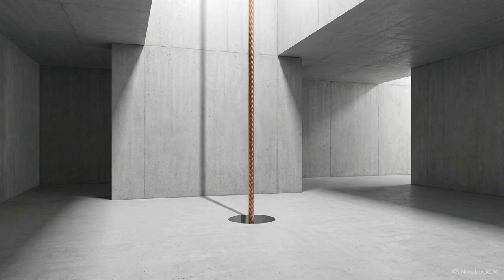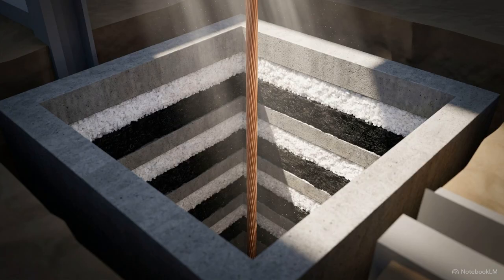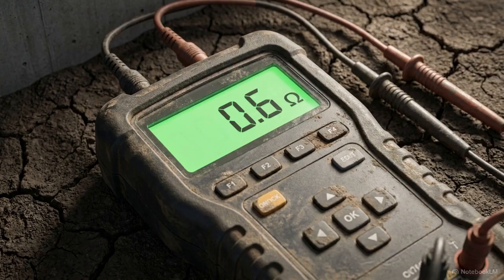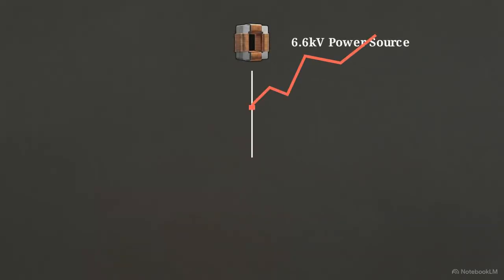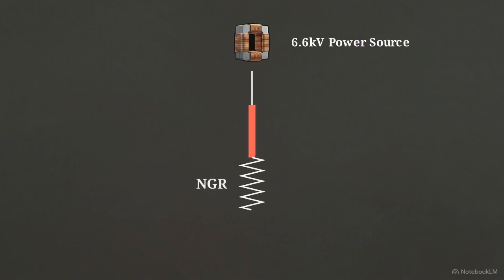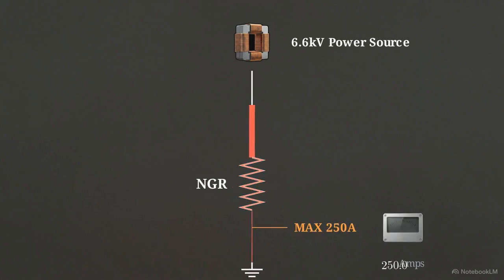Below ground, another layer of protection defends the expensive motor hardware. The entire electrical system is tied to buried pits, filled with concrete, salt, and charcoal, driving the facility's earth resistance to less than 1 ohm. This electrical schematic tracks a ground fault scenario in the 6.6 kilovolt system. Instead of allowing unlimited fault current to surge to ground, the energy is forced through a neutral grounding resistor, which acts as a strict bottleneck, capping the current at exactly 250 amps.